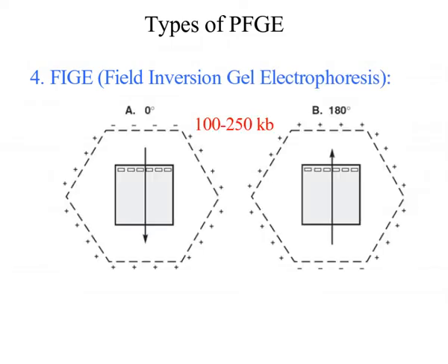Third, DR — Dynamic regulation. This type of PFGE enables reproducibility of results by compensating for changes in buffer conductivity. Fourth, FIGE — Field Inversion Gel Electrophoresis. This type enables rapid resolution of DNA in the range of 100 to 250 kilobases. FIGE involves inversion of the electric field in the forward or reverse direction by fixing the electrodes at 180 degrees.